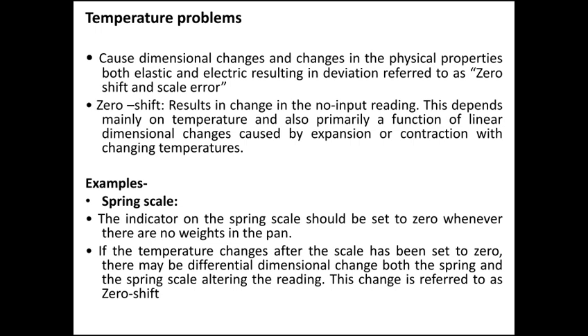Some temperature problems are also associated with this. Temperature causes dimensional changes and changes in the physical properties — both elastic and electric — resulting in deviations referred to as zero shift or scale error. Due to high temperature problems, there will be thermal expansion causing elastic problems, and some zero shift or scale error will be caused due to thermal variation. Zero shift results in a change in the no-input reading. Whenever an input signal is to be processed, due to zero shift we are not able to get the input quantity measured correctly. This zero shift mainly depends upon temperature and is primarily a function of linear dimension changes caused by expansion or contraction with changing temperatures.